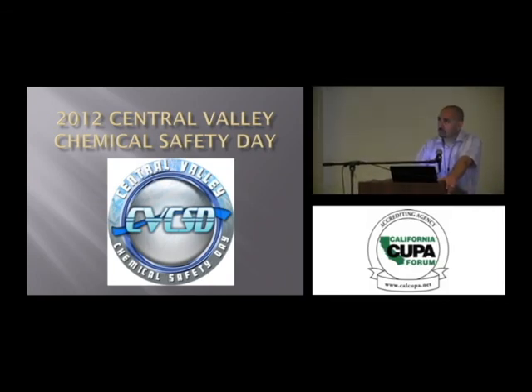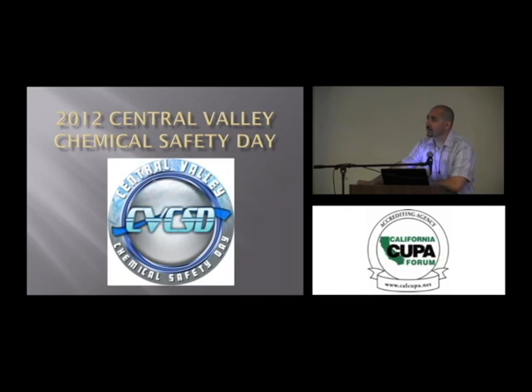But by doing this also, repair it. Yeah, I've been in plants where they've had mechanical integrity inspection. There's holes all over the place like that. And they haven't repaired them, so now we got corrosion going on where they took the plug out, accelerating it. First 5 years, man, after that, every year they should be random inspections, and then a thorough one every 5. Very good. Yep, exactly. And your pressure vessels every 5 years, checking them as well.